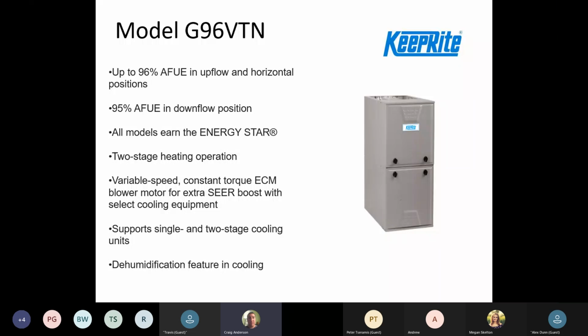If we're putting a single stage stat on it, it's going to take 16 minutes before it gets into second stage fire, high fire. So if you're doing your testing, setting your gas pressures to set your high side, you might want to jump it because it is 16 minutes. Just for setup purposes, you probably want to jump it out. And 16 minutes is a long time when you're standing there looking at a furnace. Same thing, 4-way multi-positional.